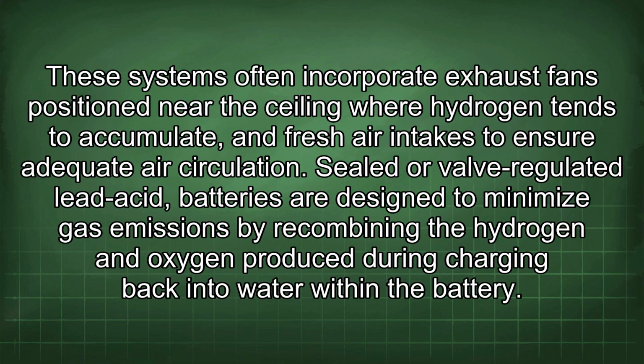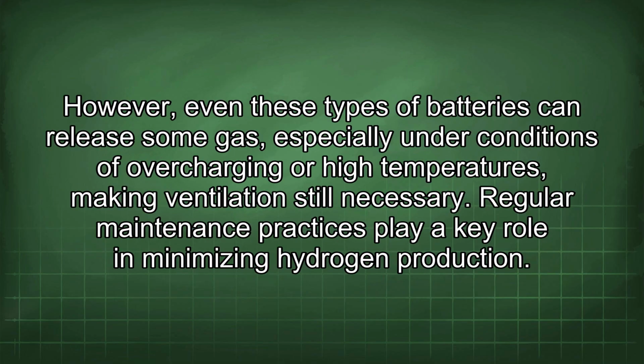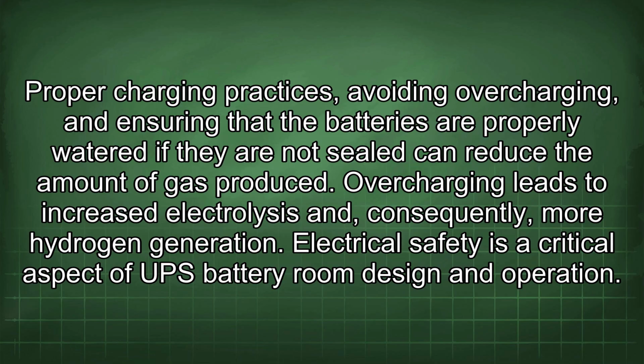These systems often incorporate exhaust fans positioned near the ceiling where hydrogen tends to accumulate, and fresh air intakes to ensure adequate air circulation. Sealed or valve-regulated lead-acid batteries are designed to minimize gas emissions by recombining the hydrogen and oxygen produced during charging back into water within the battery. However, even these types of batteries can release some gas, especially under conditions of overcharging or high temperatures, making ventilation still necessary. Regular maintenance practices play a key role in minimizing hydrogen production. Proper charging practices, avoiding overcharging, and ensuring that the batteries are properly watered if they are not sealed can reduce the amount of gas produced. Overcharging leads to increased electrolysis and consequently more hydrogen generation.